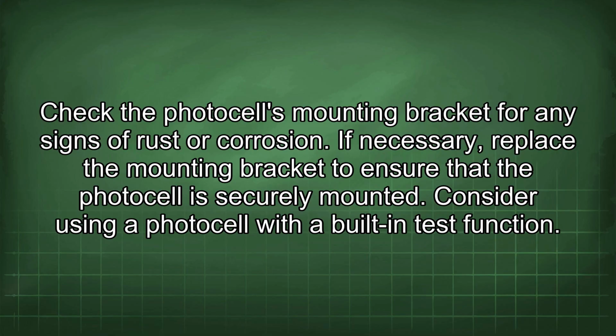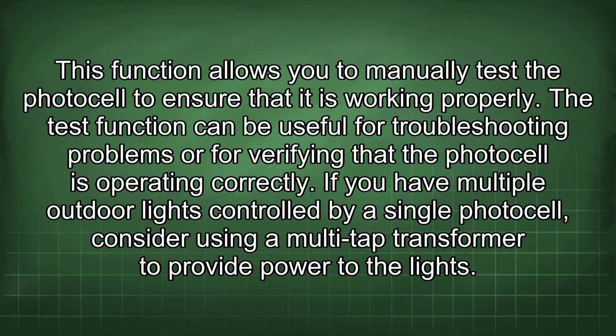Consider using a photocell with a built-in test function. This function allows you to manually test the photocell to ensure that it is working properly. The test function can be useful for troubleshooting problems or for verifying that the photocell is operating correctly.